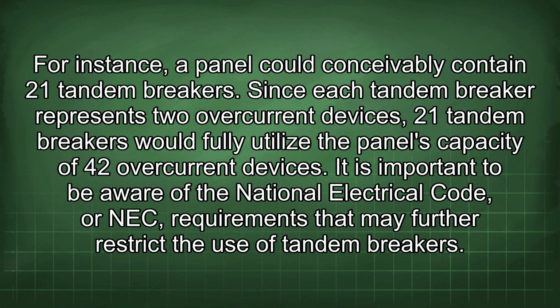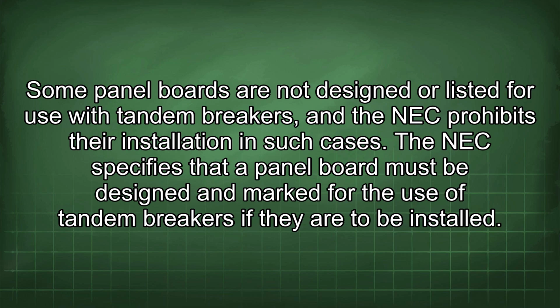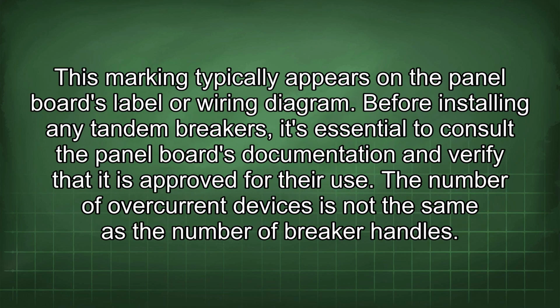It is important to be aware of the National Electrical Code, or NEC, requirements that may further restrict the use of tandem breakers. Some panel boards are not designed or listed for use with tandem breakers, and the NEC prohibits their installation in such cases. The NEC specifies that a panel board must be designed and marked for the use of tandem breakers if they are to be installed. This marking typically appears in the panel board's label or wiring diagram. Before installing any tandem breakers, it's essential to consult the panel board's documentation and verify that it is approved for their use.